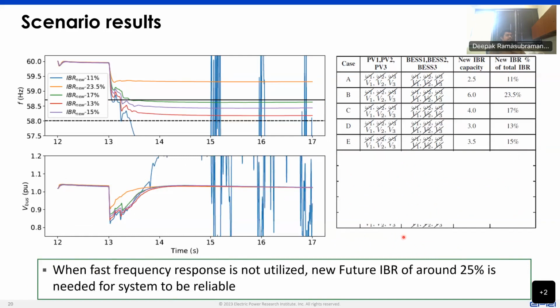So if you consider a scenario where no fast frequency response is utilized at all, but rather all the inverters are in some way legacy or conventional inverters, wherein there's still some amount of voltage control at the plant level for the PV plants, but the battery is assumed to just inject P and Q. So the battery would be legacy and the PV would be conventional, operating on a slower time scale. If you do that, then in order to maintain a stable network and meet the UFLS criteria, the under frequency load shed criteria of the system, you need around 23% of a future IBR in the network. And this lines up with other studies that have been done, which talk about the minimum percentage of a future grid-forming inverter that would be required in the network.